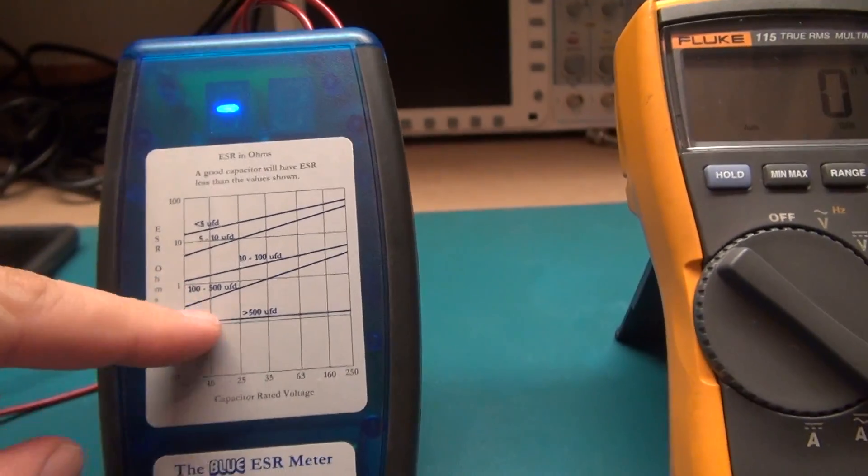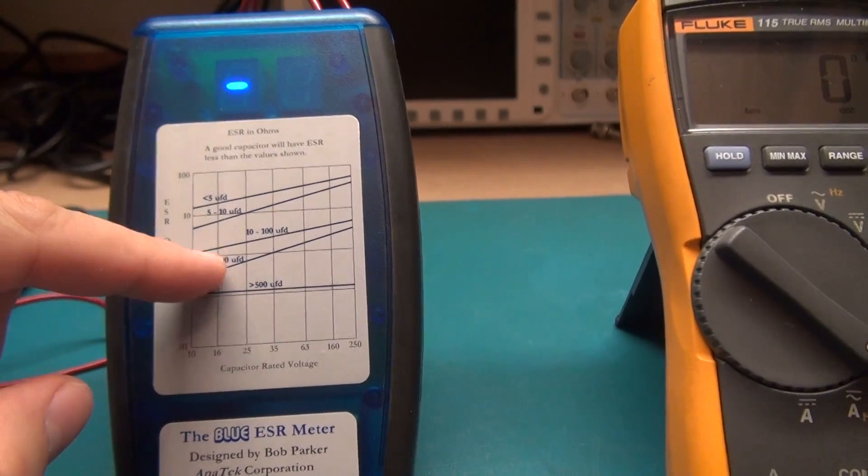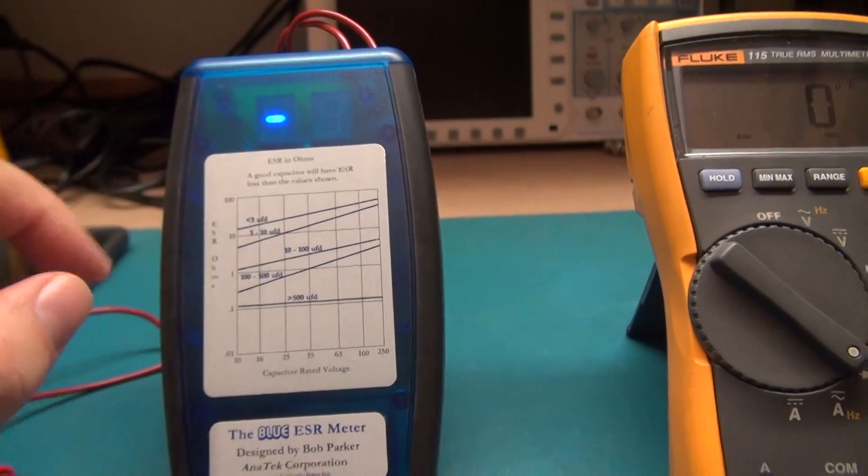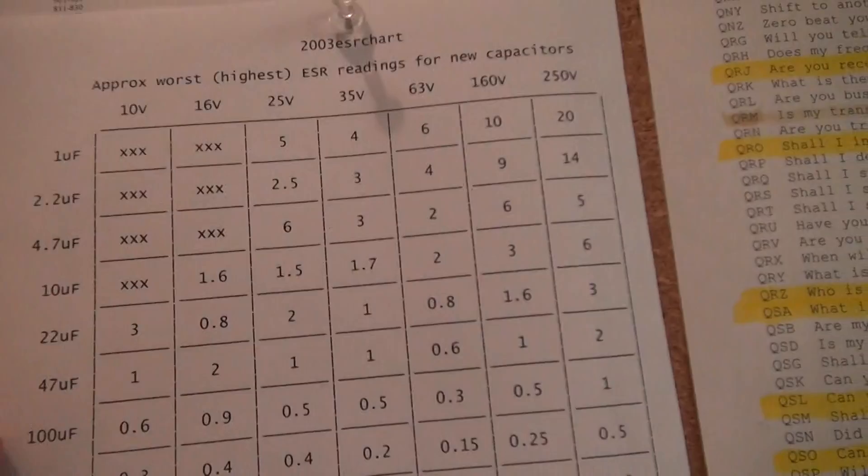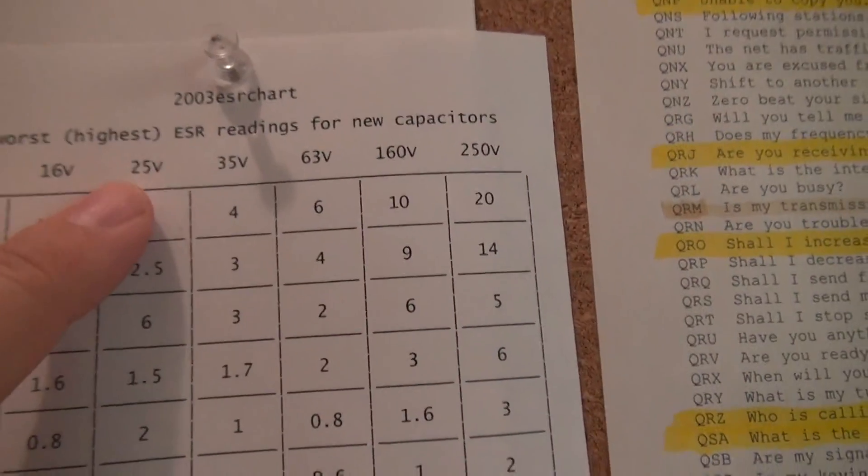I don't like to follow this chart because it's very hard to follow. I have a chart that I printed out which is right here. Basically, at 25 volts at 100 microfarad, you should probably get no more than 0.5 ohms resistance.